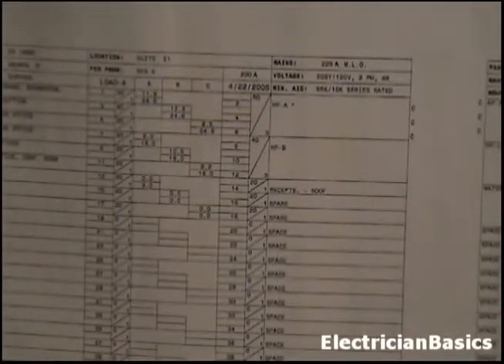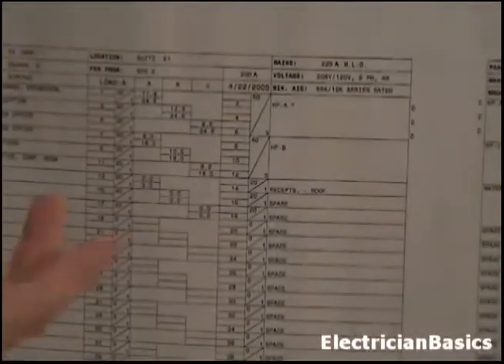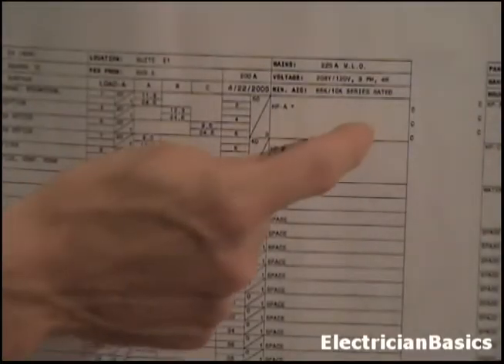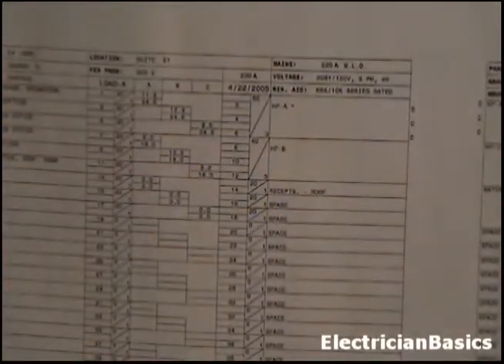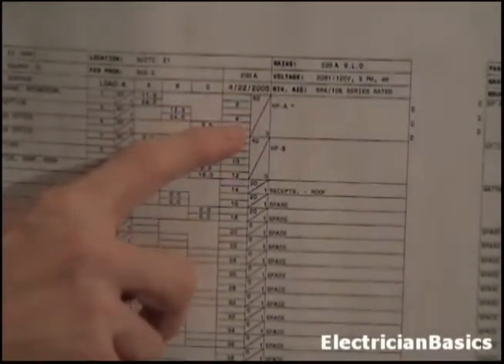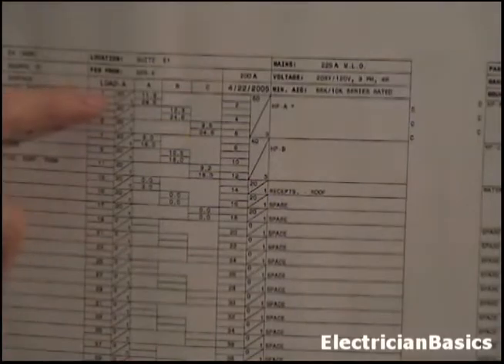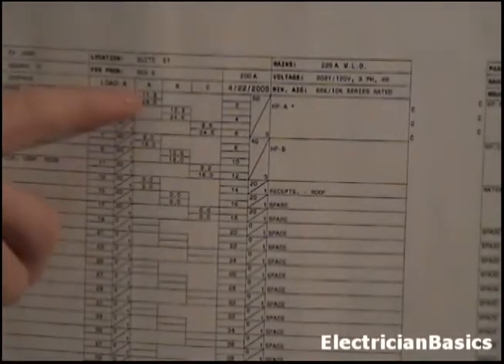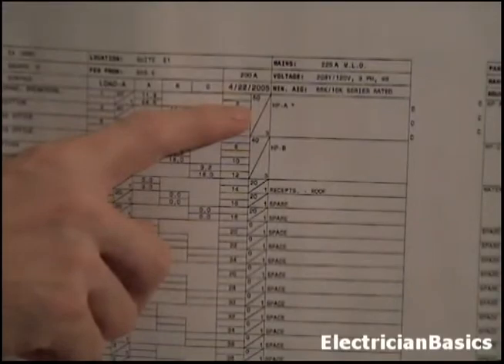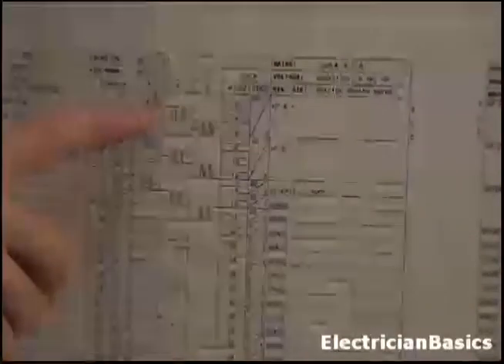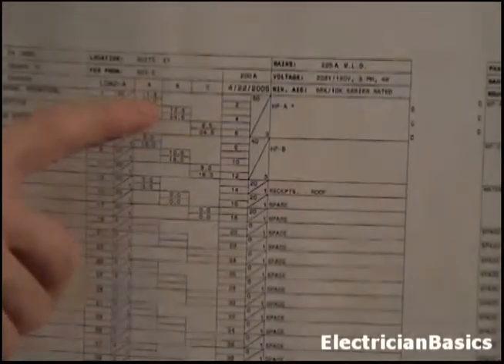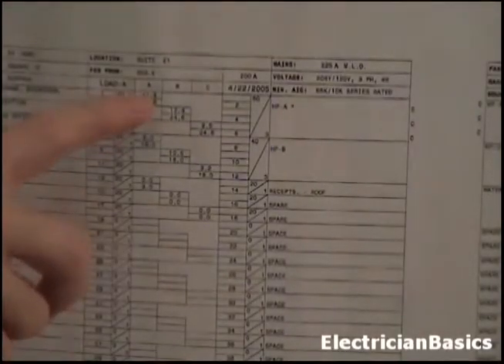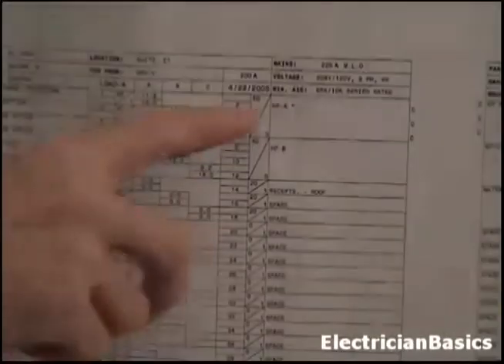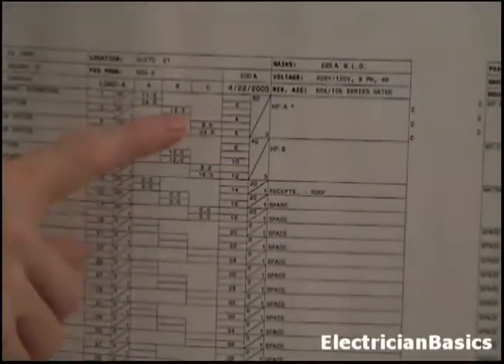Now, that only makes sense because the even numbers are going to be on one side of the panel, and you can't have a breaker that controls a circuit on this side and this side at the same time. Now, notice this. Now, it's 2, 4, 6. On this side, see how it's got kind of the top half on A? Well, here it is. It's also phase A. So that's that bottom number there. So in other words, the number for the odd on phase A is over here, and the number for the even is over here. And you can see it through here and here.